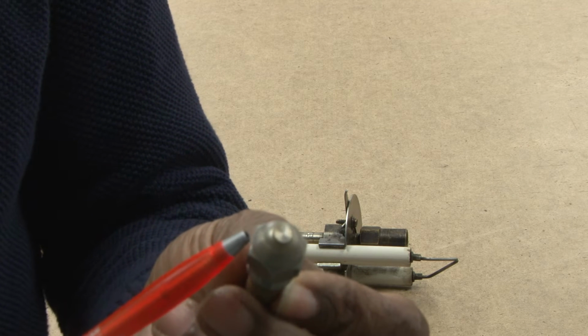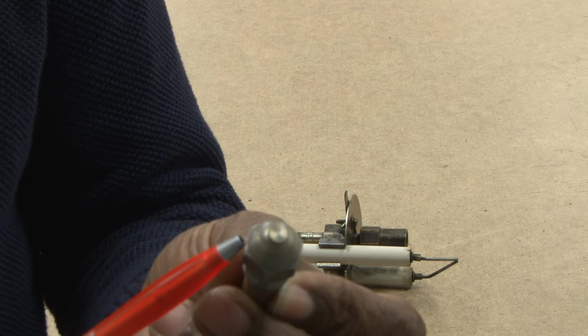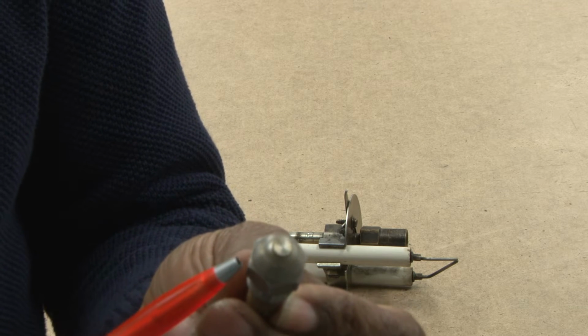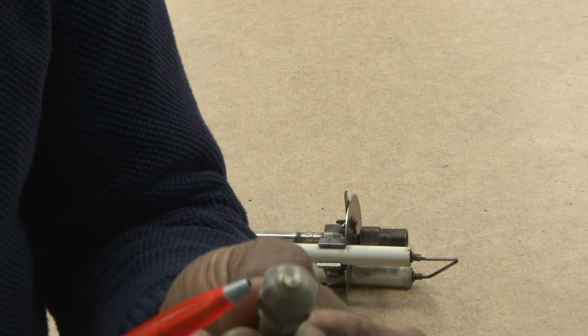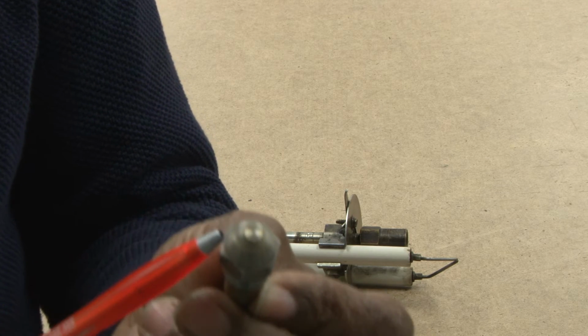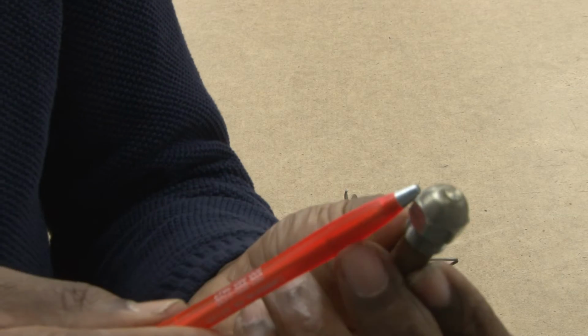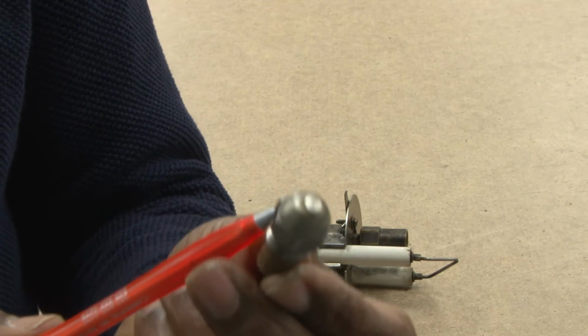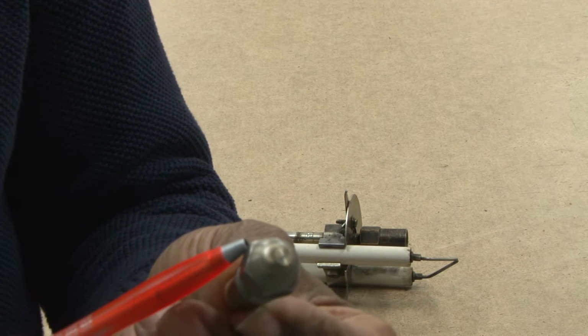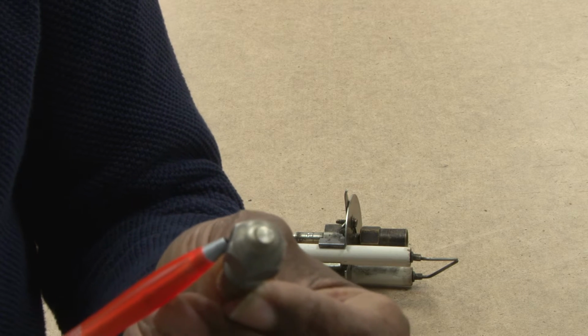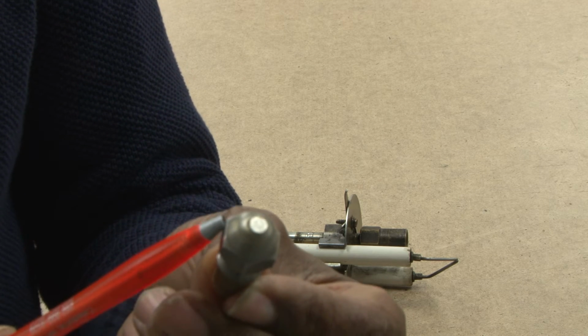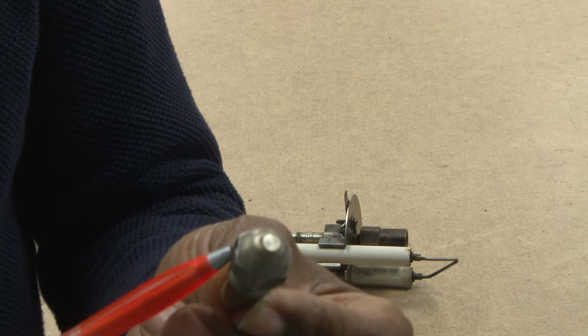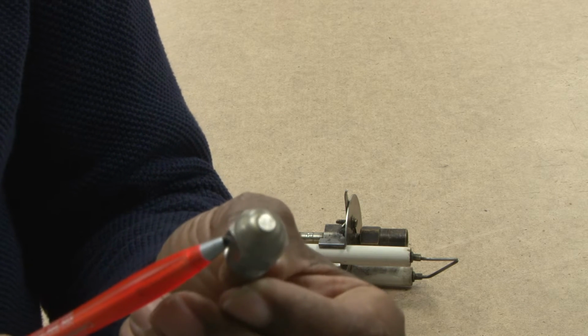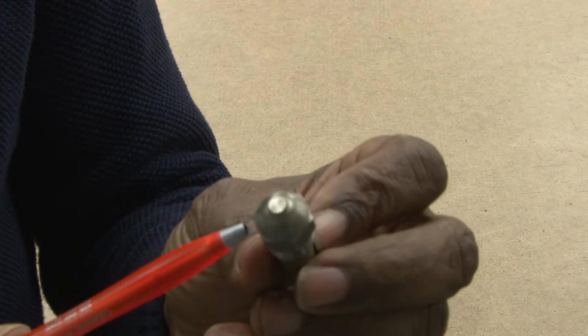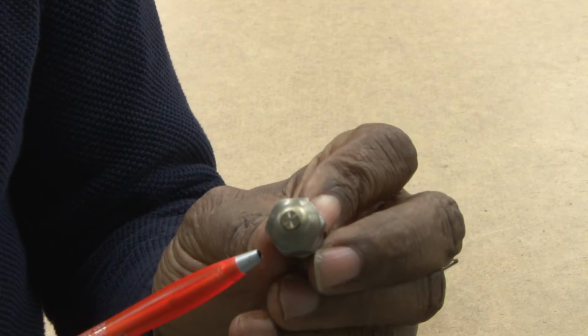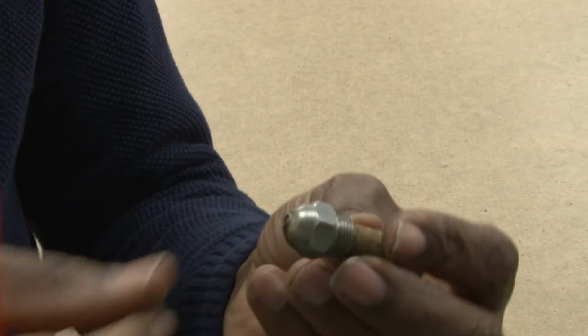oil. And if you consider 1 gallon of oil is 140,000 BTUs, this nozzle will create about 70,000 BTUs per hour. Also, it's designed to have a spray pattern of 70 degrees. It has an H on it, which stands for hollow. It will be a 70-degree flame, and inside of the flame will be hollowed out. So they designed these for certain purposes based on the heat exchanger.